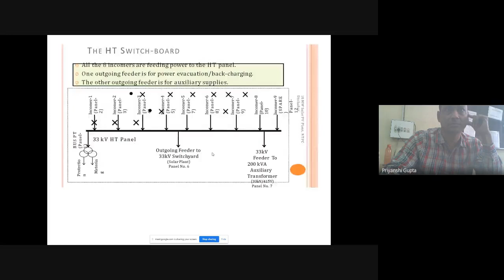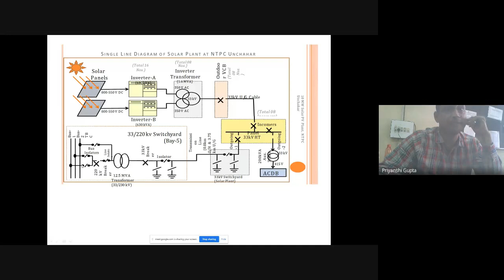Let me go back to the previous slide. So this is the transformer and this is the outdoor switchgear. From here there is a 33 kV indoor switchgear, and from here we're feeding a small switchyard, and through this transmission line we transmit electricity to the existing switchyard.